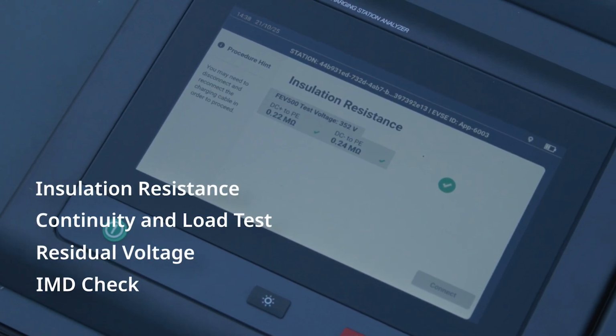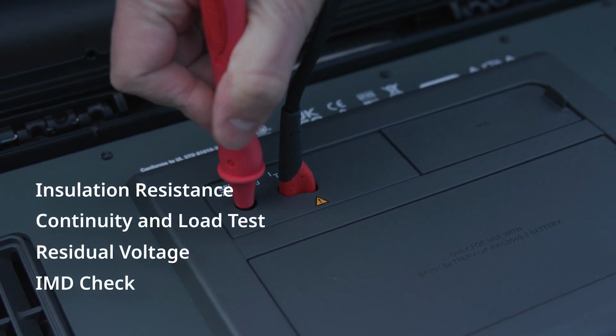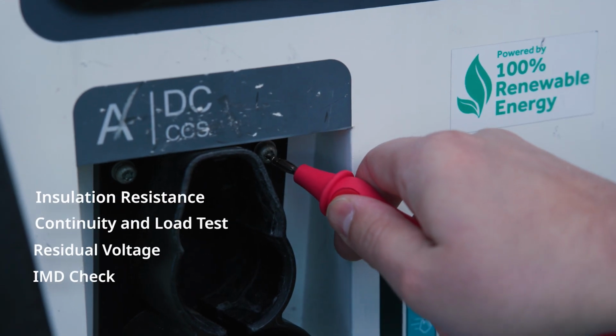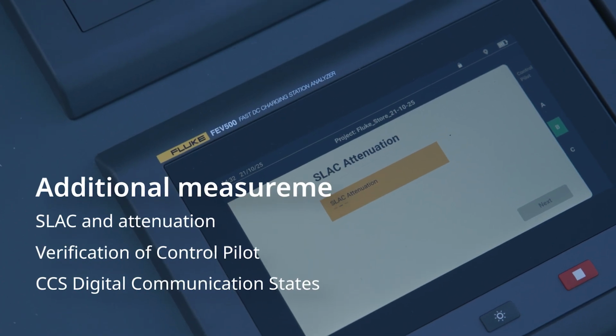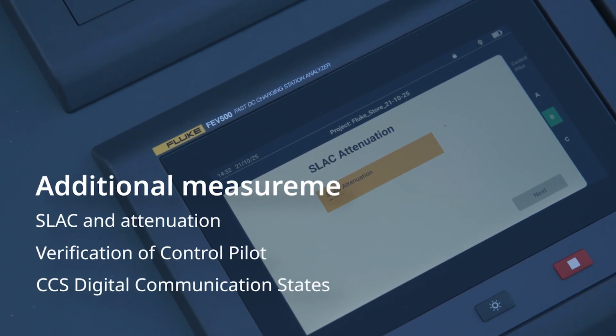Tests include insulation resistance, continuity and load test, residual voltage, and IMD checks, all meeting IEC standards. Additional measurements include SLAC and attenuation, and verification of control pilot and CCS digital communication states.